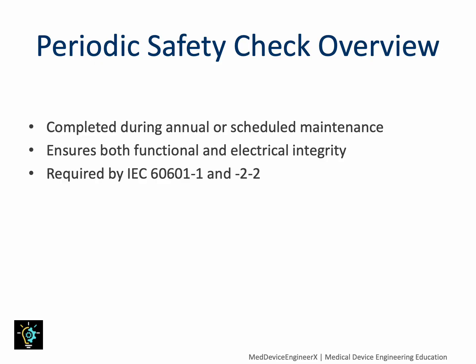Periodic safety checks are part of every preventive maintenance cycle. The goal is to verify that the generator remains both electrically safe and fully functional. Technicians confirm visual condition, grounding, and leakage limits. This process aligns with IEC 60601 standards and manufacturer guidance. Each test protects patients and staff from possible hazards like insulation failure or poor grounding. Think of it as a structured routine to catch small issues before they become performance problems.